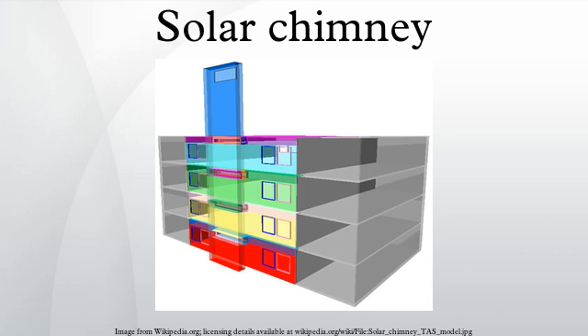The principle is to allow water to evaporate at the top of a tower either by using evaporative cooling pads or by spraying water. Evaporation cools the incoming air, causing a downdraft of cool air that will bring down the temperature inside the building.